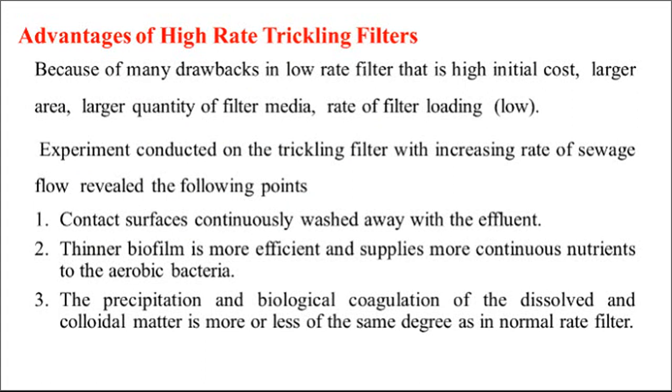Because of many drawbacks in low rate trickling filter, that is high initial cost, larger area, larger quantity of filter media, and low rate of loading, we can say the low rate trickling filters are not that much popular. Also, the experiment conducted on the trickling filter with increasing rate of sewage flow revealed the following important points.